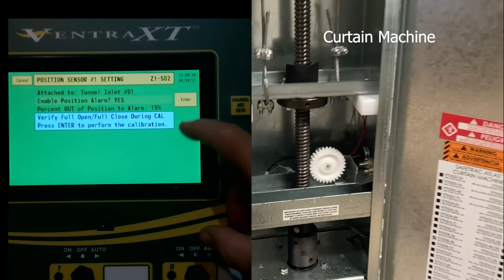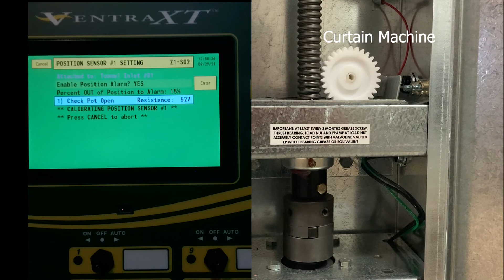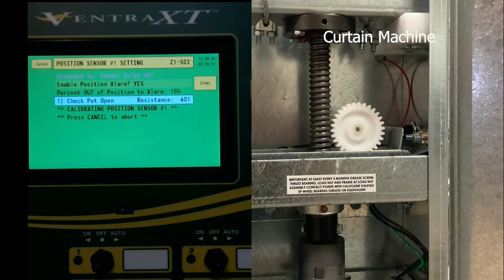And now we're going to press enter to let the controller automatically calibrate the position sensor. So press enter to begin, press enter to start and perform the calibration. Now it is going to check open and check close to make sure that it is traveling in proper directions, and then it will fully open and then fully close the entire tunnel inlet before it completes its calibration.